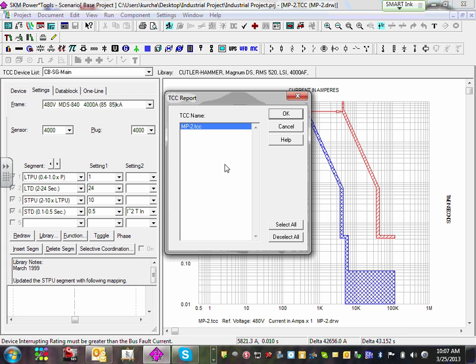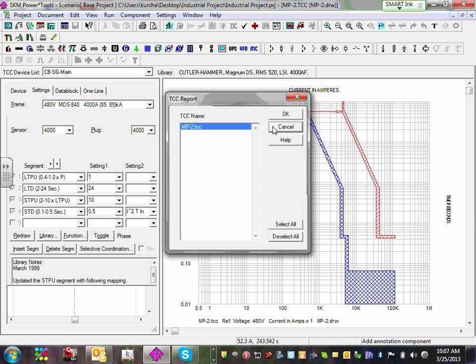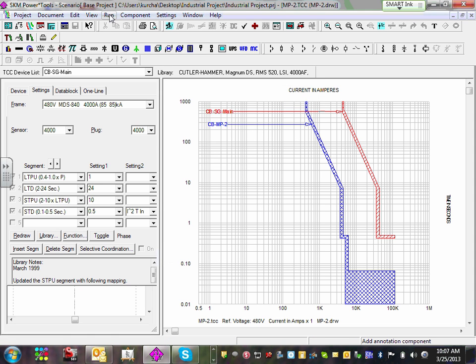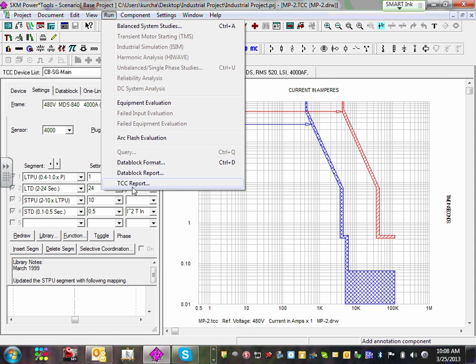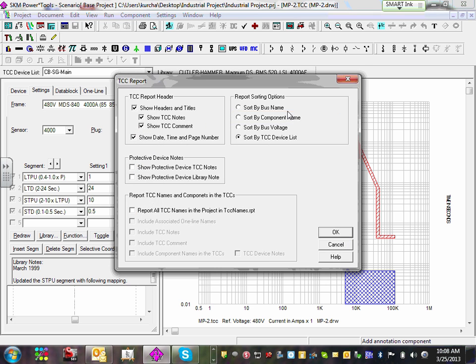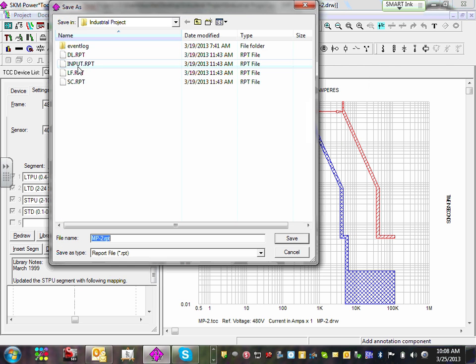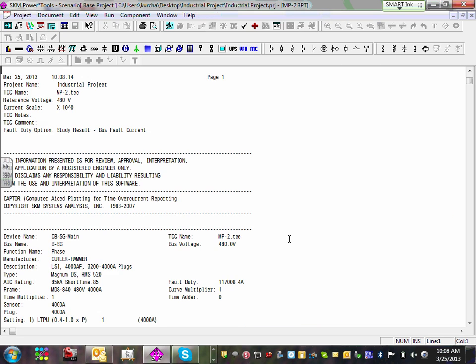That will run a report for you that shows all these settings, which you can give to the electrician so they can set it up. One more time: when you're done with coordination, or at any time, it doesn't have to be, run TCC and okay it, and that tells you do you want to run all these. Take the default and run it. Where do you want to put it? It always puts it in one location, guys, and names it the same thing, MP2. Take the default and hit OK. This is how it opens it for you.